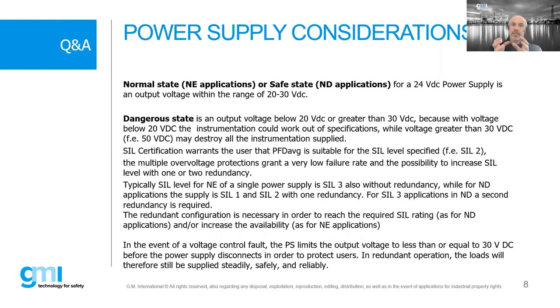So the SIL certification grants that the unit is working for the specified SIL. You have this specification for the SIL you want to reach, and it works for that certain SIL specification. And the multiple overvoltage protection grants that this SIL has to be respected. So typically the SIL level for a single power supply is SIL3 without redundancy, as we have seen. But for normally de-energized, where you want to energize in case of failure, it is only SIL1, and SIL2 is only granted with redundancy. So redundancy is very important for granting the SIL rating.